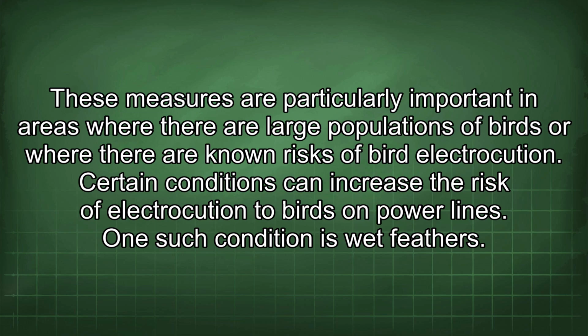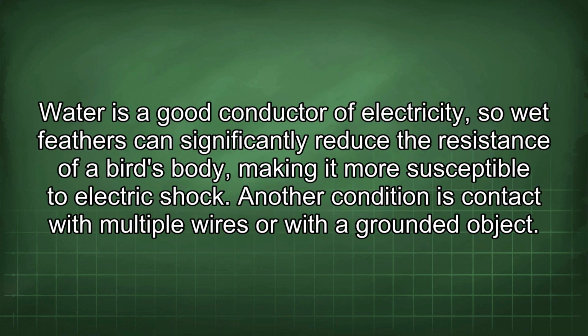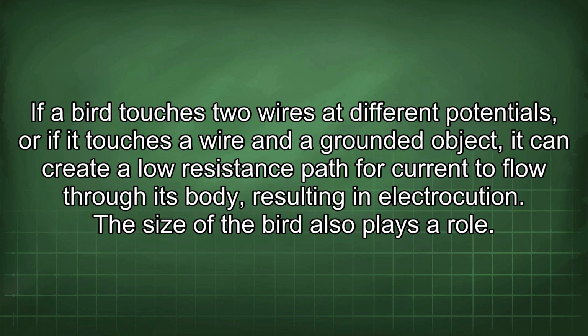One such condition is wet feathers. Water is a good conductor of electricity, so wet feathers can significantly reduce the resistance of a bird's body, making it more susceptible to electric shock. Another condition is contact with multiple wires or with a grounded object. If a bird touches two wires at different potentials, or if it touches a wire and a grounded object, it can create a low resistance path for current to flow through its body, resulting in electrocution.